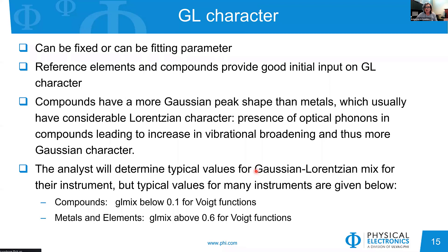When you don't know how to start, reference elements and compounds provide really good input. As a rule of thumb — and I'll say this throughout the webinar — references tell you a lot about your instrument and the settings at which you acquire a spectrum. The general recommendation is that compounds have a more Gaussian shape (around 0.1 GL mix), while for pure metals and elements there is more Lorentzian contribution. But you need to understand your own materials and instrument to use good judgment for that parameter.